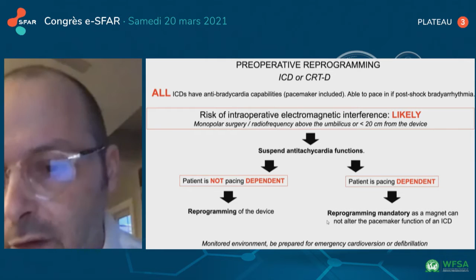If the patient is not pacing dependent, you can use, of course, your cardiologist or a magnet. If the patient is pacing dependent, the reprogramming will be mandatory because the magnet cannot alter a pacemaker function in an ICD, which is not, of course, the case for a regular pacemaker. Deactivating an ICD should be done in a monitored environment, and be prepared for a backup cardioversion.